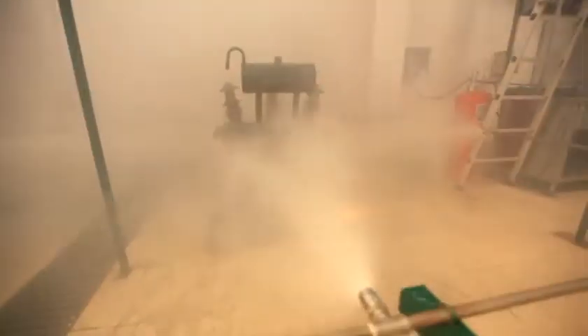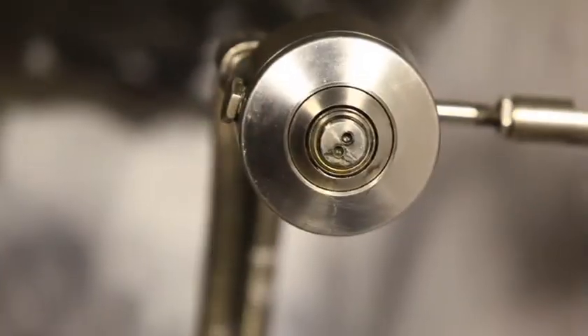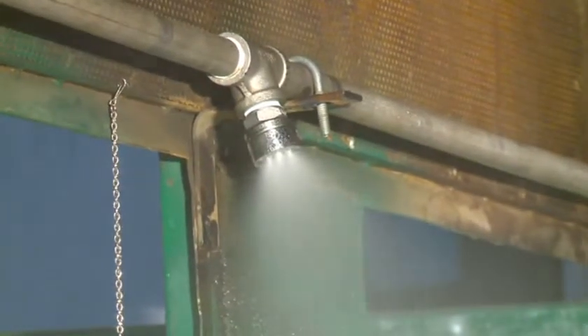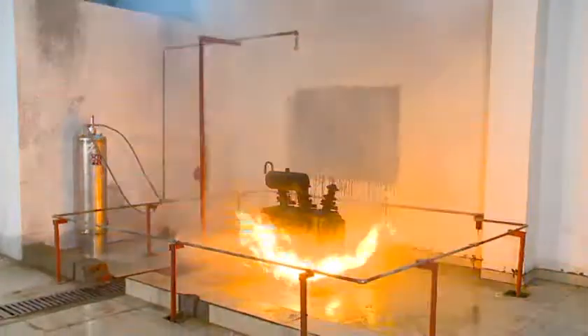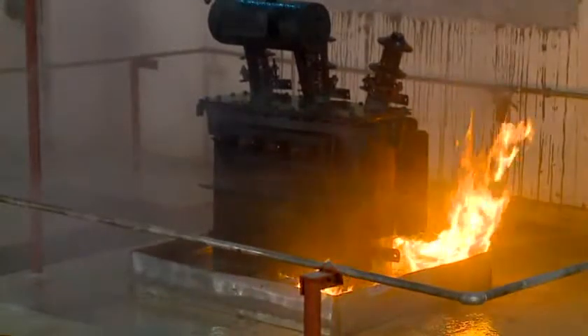We call that firefighting technology water mist. Using water mist technology, we realized we could alter the very form of water, converting it into a very fine mist, thereby making it an outstanding physically acting agent with exceptionally high heat absorbing capacity due to high latent heat of vaporization. Here's how water mist works.